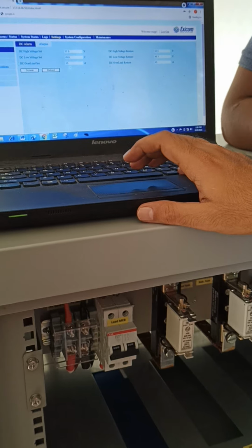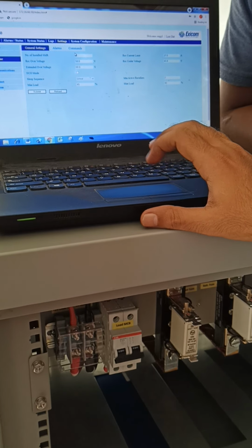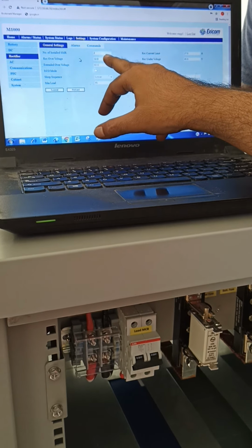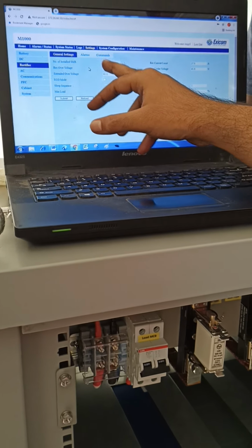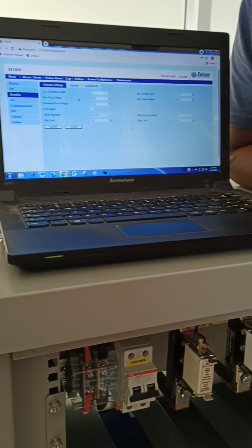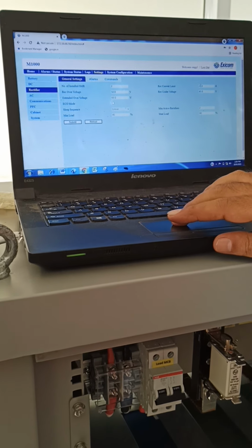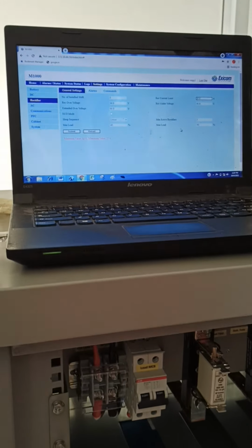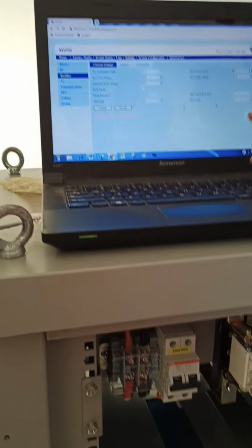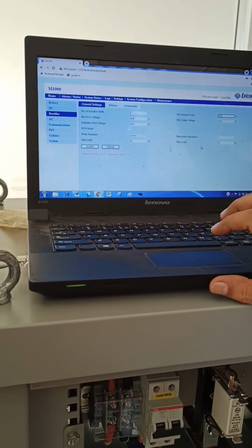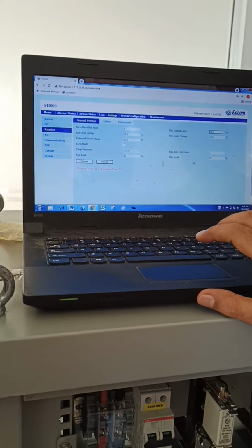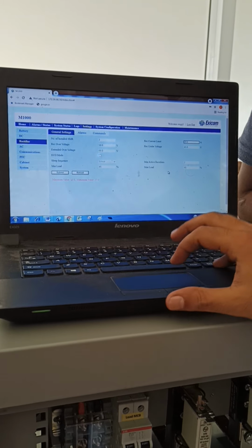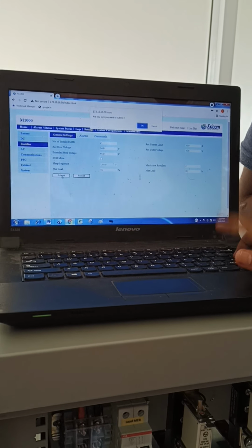Now DC settings, voltage and everything is there. Now this is the rectifier settings. In the rectifier setting, you have to see the number of rectifiers installed, SMR installed. Somewhere 2 numbers, somewhere 4, so you have to mention 4. Here the voltage is showing 27, but one rectifier, what is the rating? 25 amps, but it's mentioned max 27. So we'll put 20. One rectifier will take 20, it should not reach up to 25, so its life will be more. Submit. 20 means 80%.